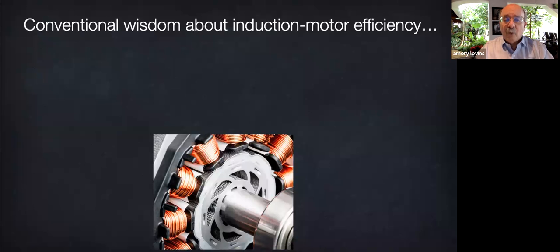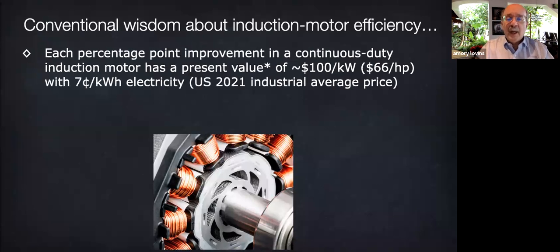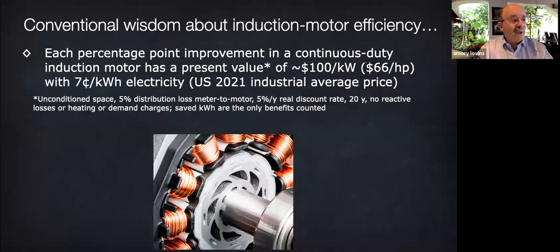The value of more efficient motors is high. Each percentage point gain to a motor that runs continuously in a typical American industry is worth about $100 per kilowatt of motor capacity. So how many percentage points to be multiplied that way can we save by using better motors?